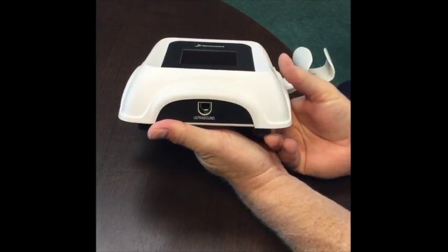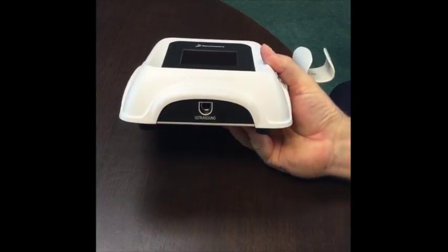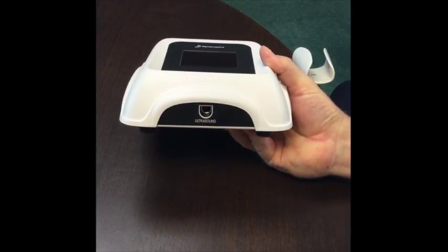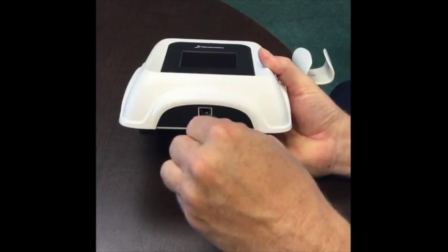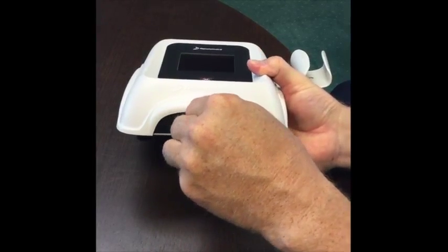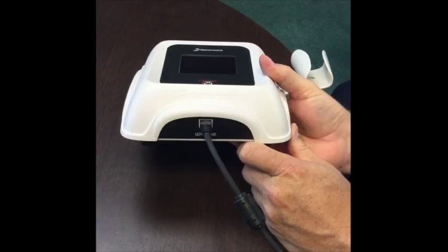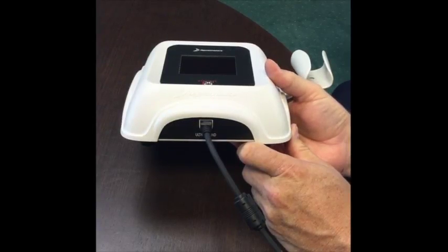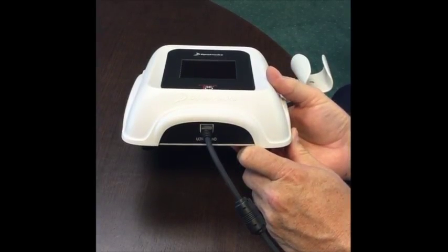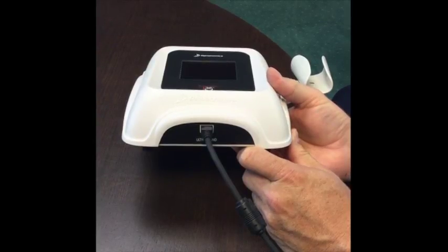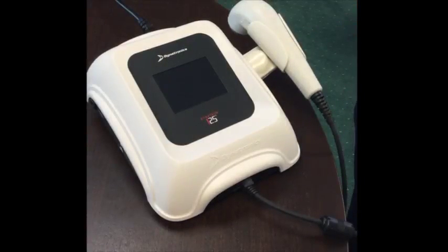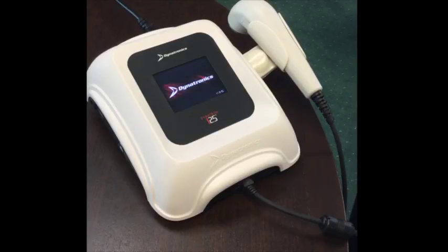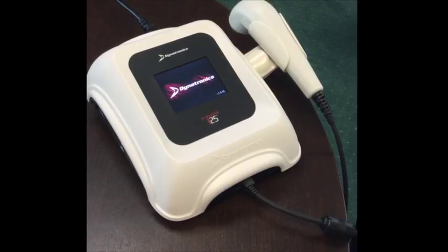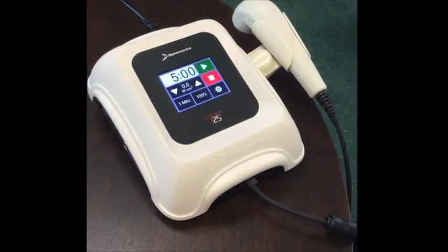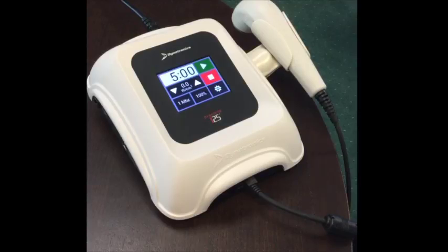The Dynatron 125 will have smart head technology and allow the use of a 2, 5, or 10 centimeter head to be plugged in directly into the device. Those parameters for the sound head calibration are located in the head and will not need manual calibration entry. As we turn on the machine, initially what we'll see is the Dynatron splash screen showing the logo. Next will come up the operation screen, whose controls are very simple and intuitive to operate.